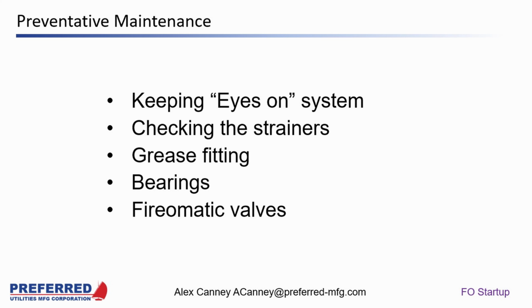But let's say the day tank is completely full and you're below your pump off and you never quite make it down to pump on, or you do, but it's halfway through the test. This allows you to have the maximum amount of fuel in your day tank without actually being in high level alarm, so that if an emergency happens, you actually have that working amount rather than being just above maybe the pump on point. And this was a standard program that I was working with.